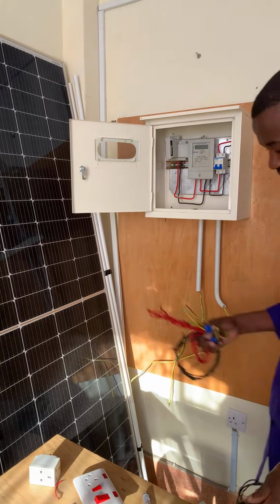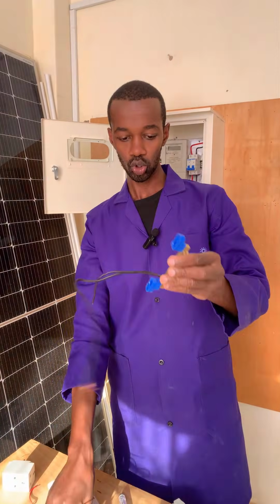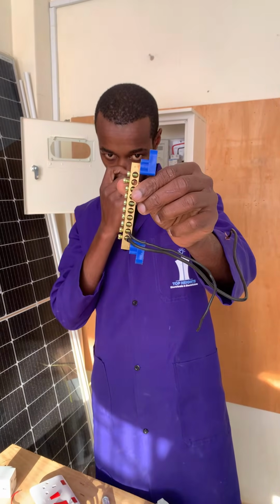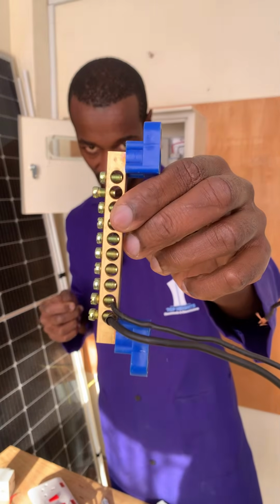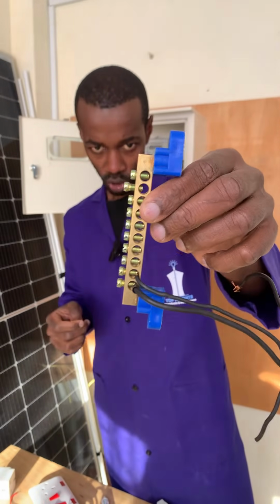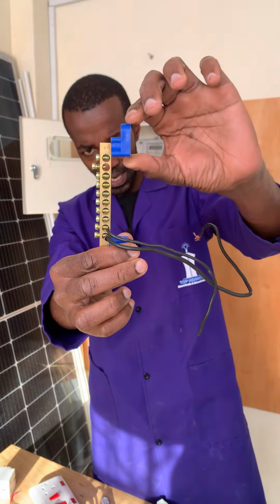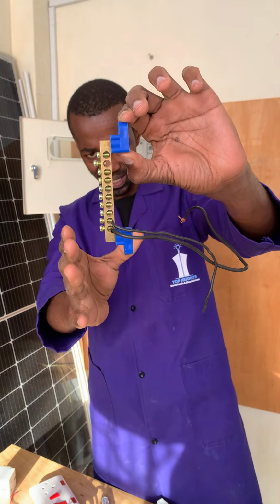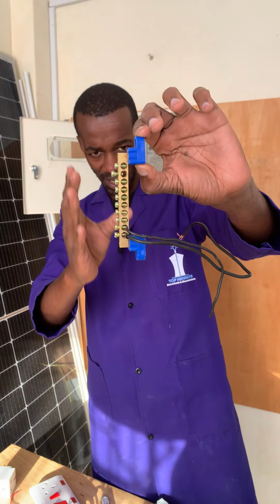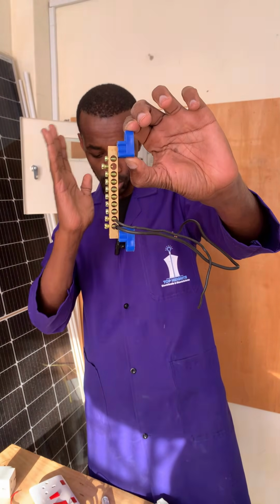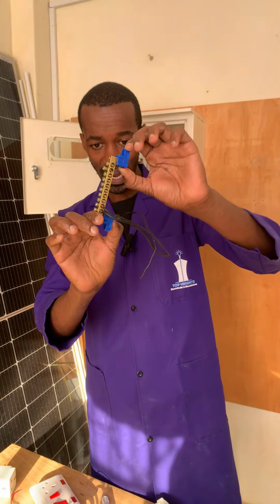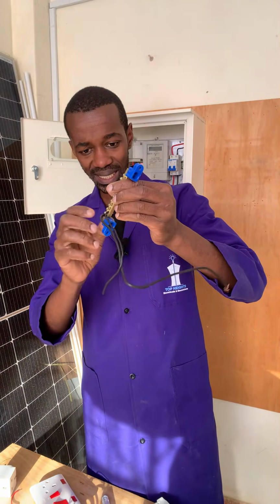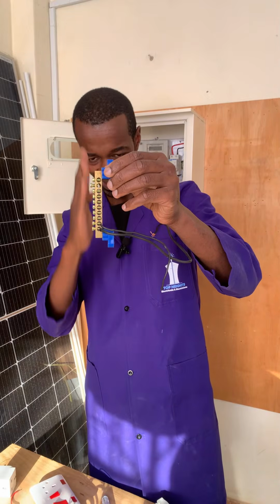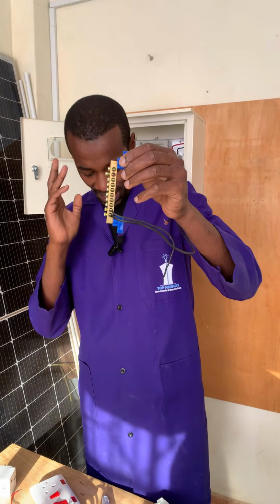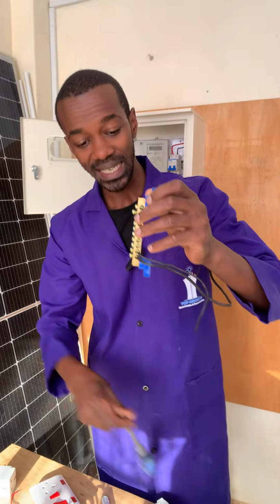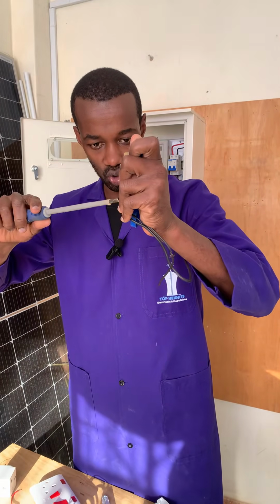Now, my top bosses, we have these cables, and we also have this important connection right here. I don't know whether it is closer to the camera. This is what is referred to as a neutral bar. In many cases, it is connected or located in the distribution board. Majority of people make a mistake whereby, while connecting the neutrals here for their specific circuits, they are not very keen in tightening this neutral bar.